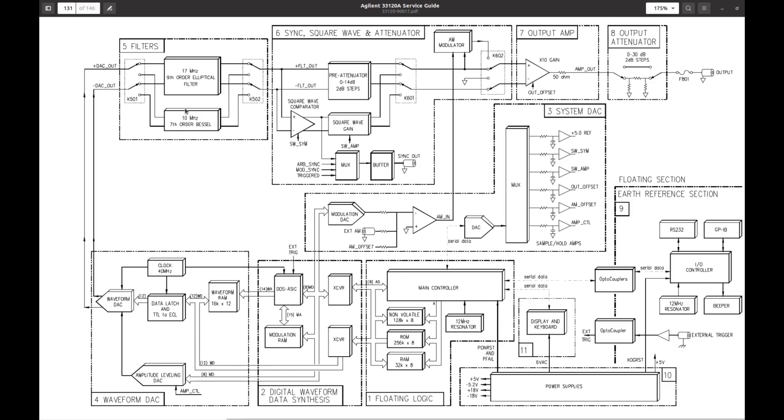Waveform DAC produces differential output, which goes to filters. And there are two signal paths here through this 17MHz low-pass filter and 10MHz low-pass filter, to get rid of high-frequency noise. The output of this is still differential and goes to this pre-attenuator, 0 to 14 dB in 2 dB steps.